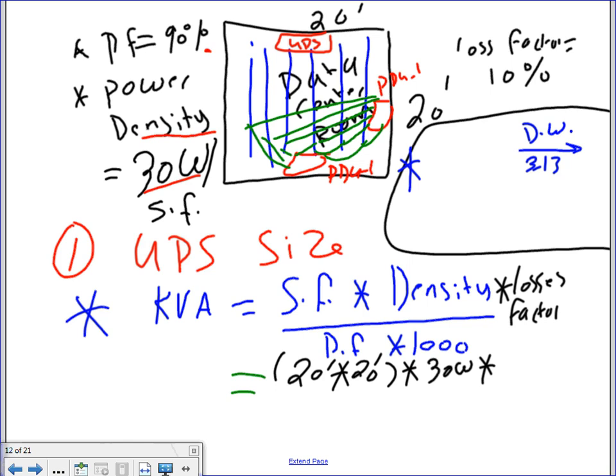So I need to increase my system by 1.1 because of the loss factor, right? With a 10% loss factor, I need to increase my system 10% to accommodate for it. Divide by the power factor, which is 0.9. Divide by 1,000, of course, so it converts everything to kVA. Ladies and gentlemen, I don't have the answer for this because I changed them. I need two people to give me the answer, please, because I changed a few things here.